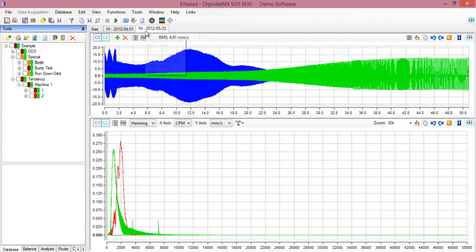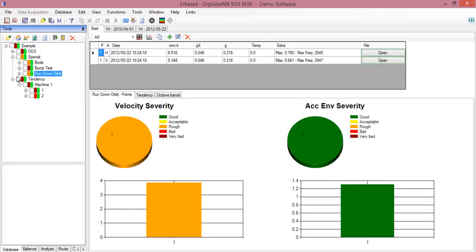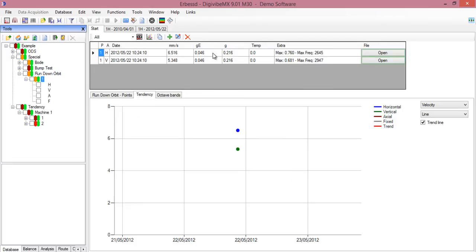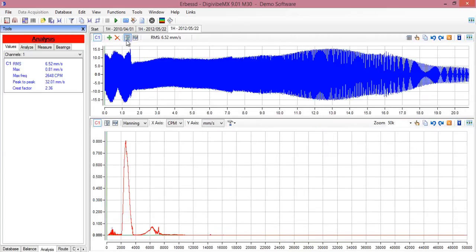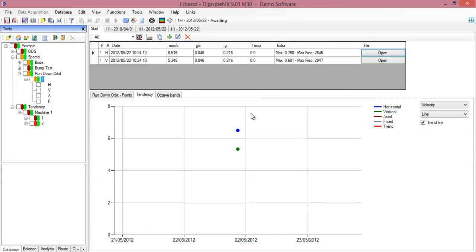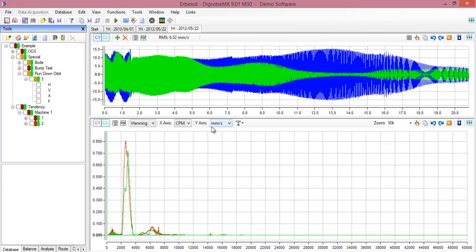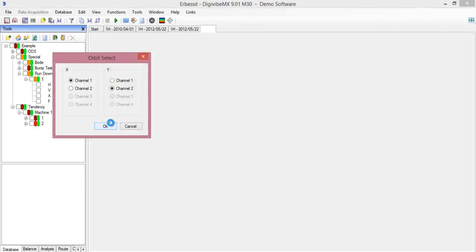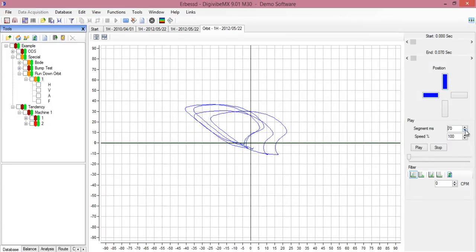Another thing you can try is to open the rundown orbit. This is an orbit recorded during a rundown analysis. We will open the horizontal file first and then the vertical one. Now we make the orbit. This is a rundown orbit, that's why it looks so. You just select the segment, click play.